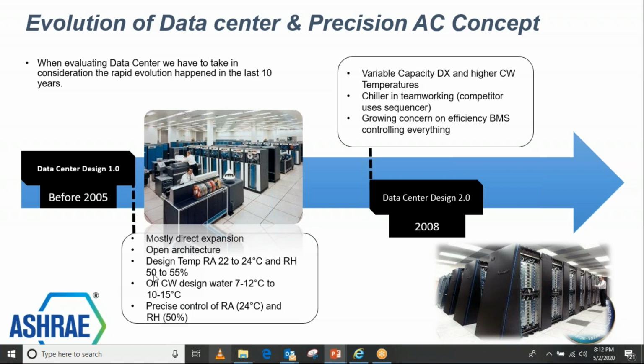Another challenge was that even on the control part of the precision AC which was used, those were controlled from the return air. When you have a server room and your cooling units are installed in the plant room, those units were controlled from the return air temperature. So supply used to be much lower, maybe around 10 to 12 degrees centigrade, and return air used to be around 22 to 24 degrees centigrade.